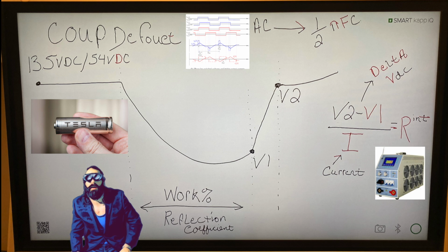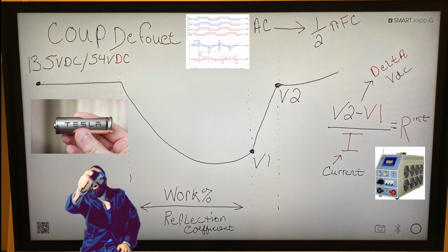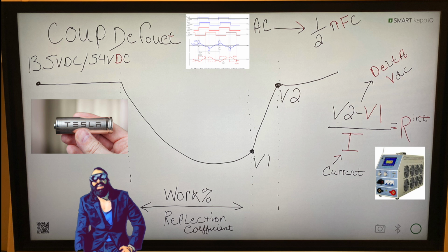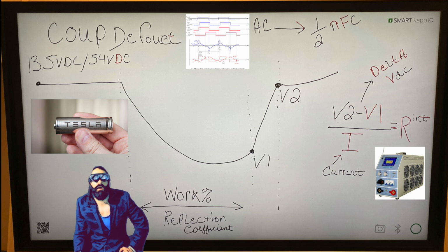implementation. Why? How can this do this? Well, instead of just doing one of these voltage drops like this, what it would go out and do is 5 to 7 or 10, and then drop the 2 highest and 2 lowest and average the middle 6. And this again is trying to make up for inconsistencies, inadequacies, and inefficiencies in three-phase UPS power systems, and it can cause quite a few problems.